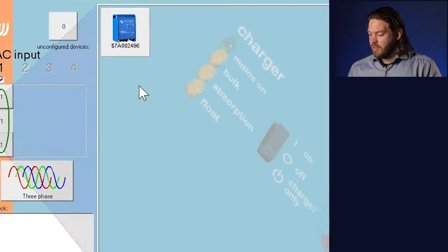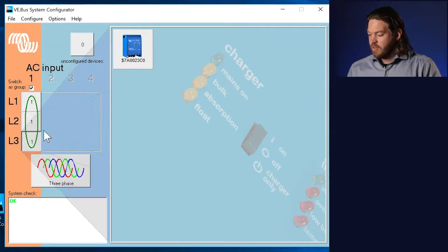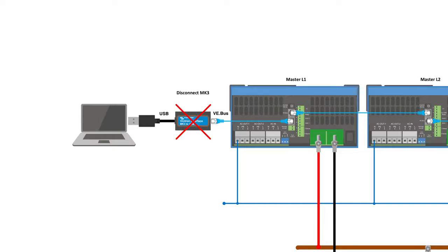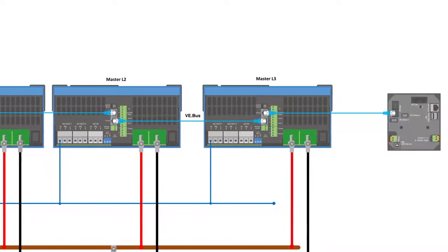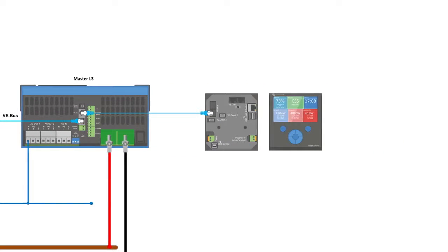And we're done. Now you can repeat that procedure for the third and final unit. Once we've got the system configurations loaded into each of the multis through VE Configure via the VE Bus System Configurator tool, we can disconnect the MK3. Once the MK3 is disconnected, we can then reconnect the color control or other accessories like the digital multi-control. This is an important step if you have a GX device to confirm the system's working as expected.